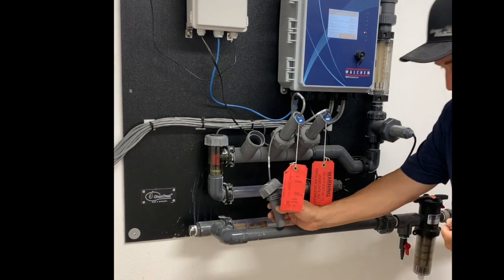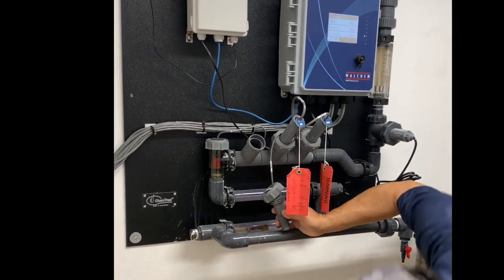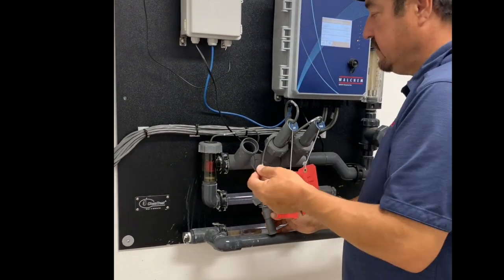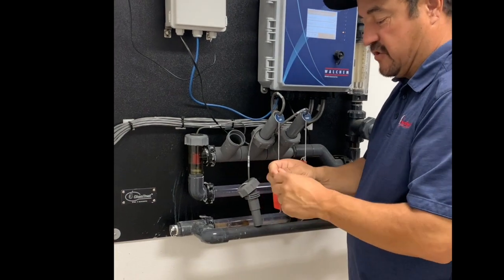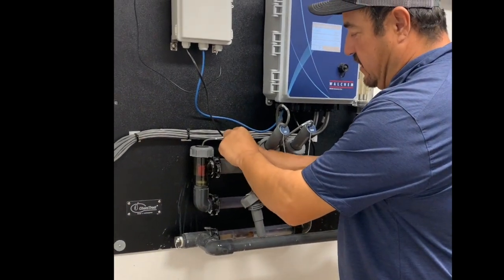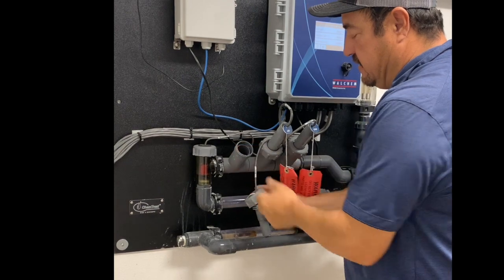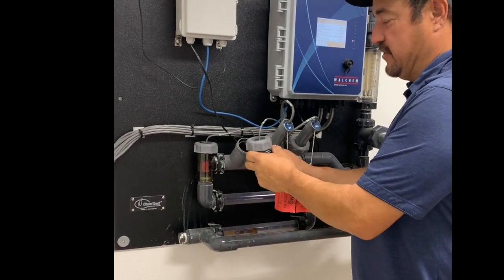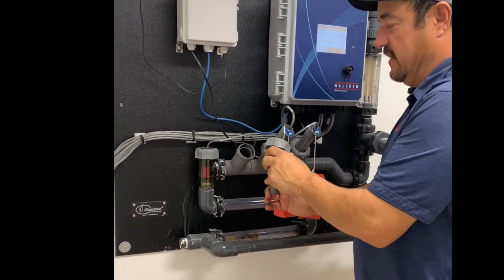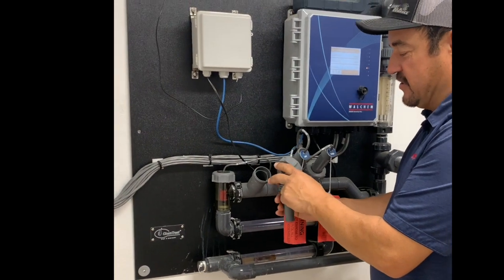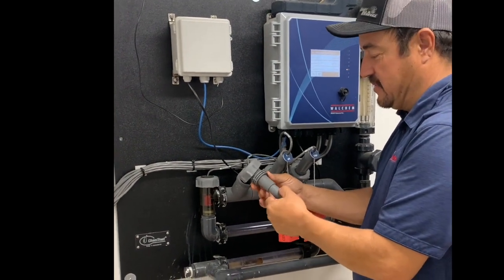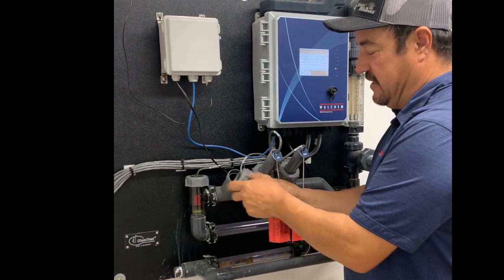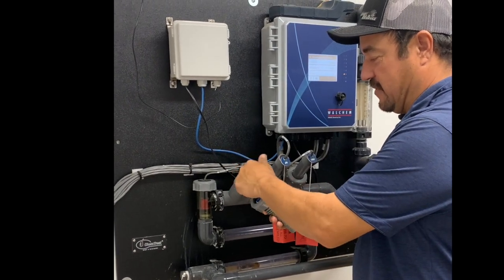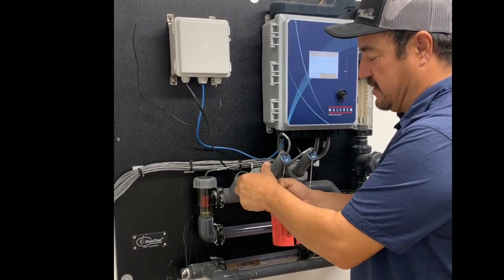Now, one thing that you noticed possibly, and it was a good thing, is that this O-ring fell out. What's really important is that you need to make sure that the O-ring's inside the unit onto the housing. Many times we'll lose those and we'll put them back in and we'll forget that it's on there. We keep wrenching it down tight and it keeps leaking. You don't need to put any duct tape on it or any tape or Teflon or anything like that. Just make sure the O-ring's in there.